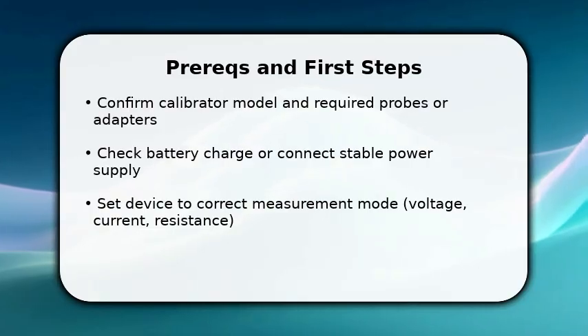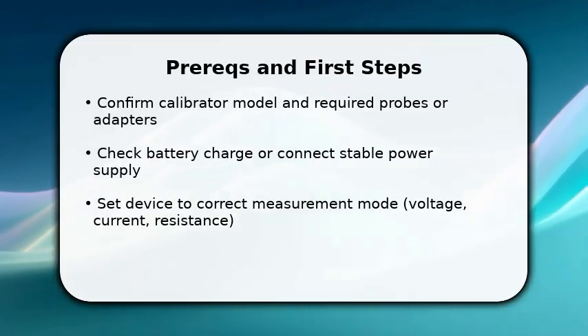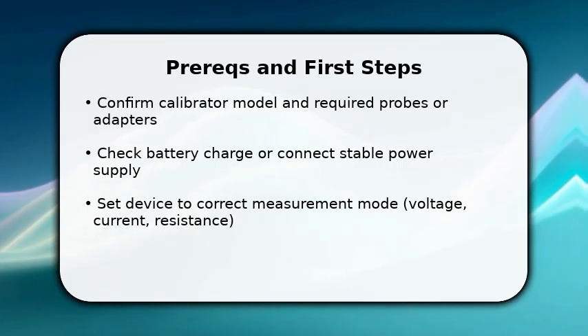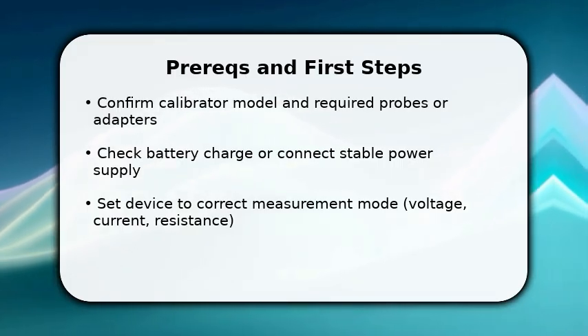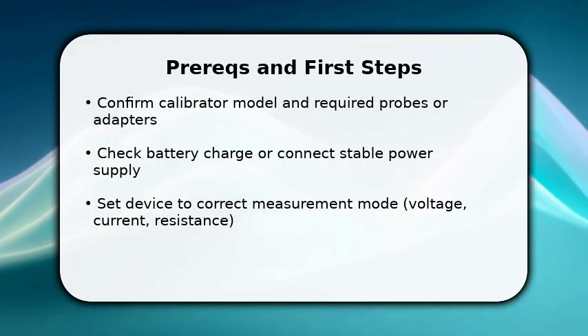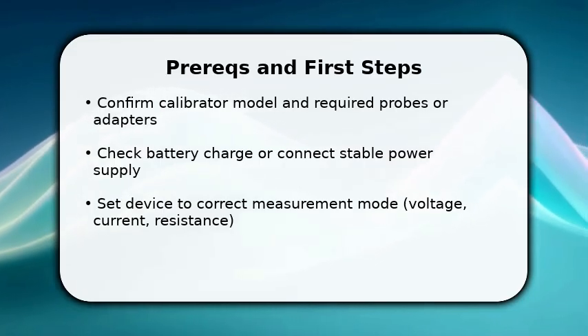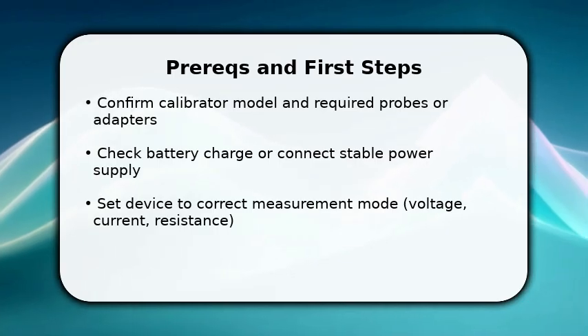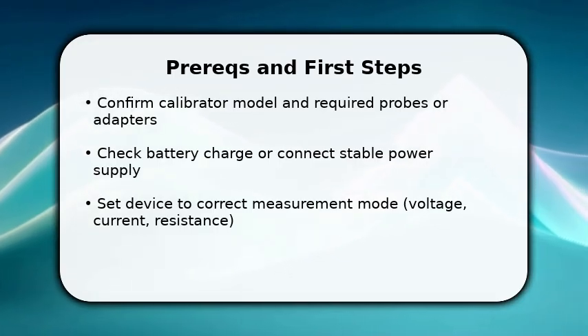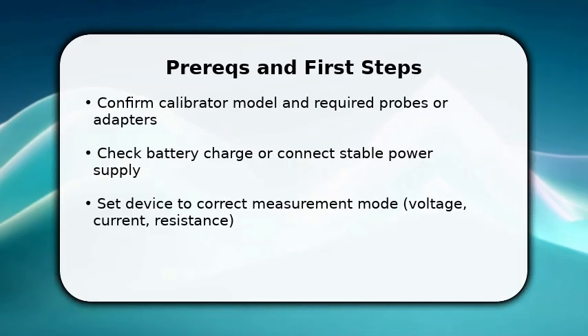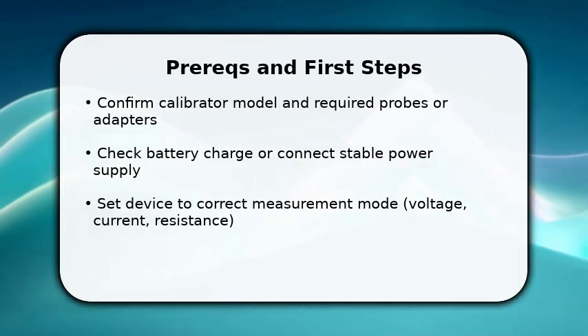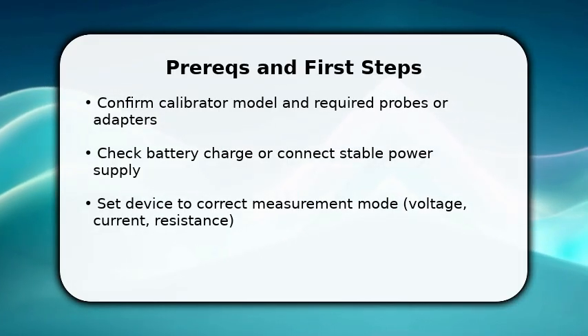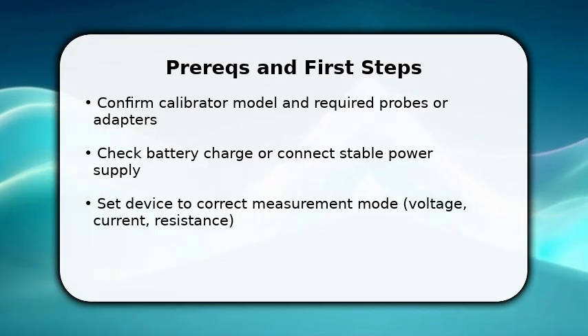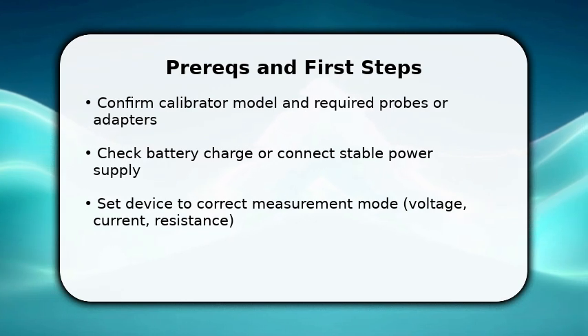You start by verifying the calibrator model and what probes you need. This prevents mismatches that waste time. Once you have the right adapter, make sure batteries are charged or plug into a stable outlet to avoid interruptions. Next, select the correct measurement mode, voltage, current, or resistance, because the device applies different internal references for each. While connecting leads, observe polarity and secure contacts. A loose connection will skew results. After these checks, you're ready to initialize the calibration sequence.